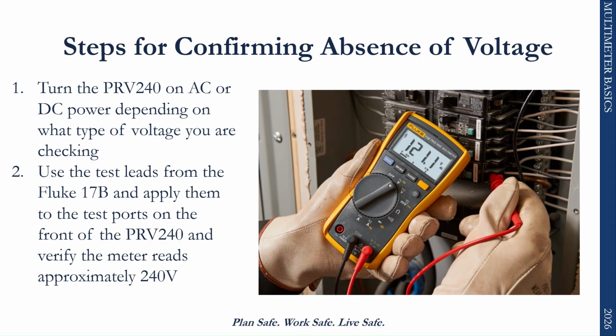The first step in the live-dead-live process is verifying that your meter is functioning properly. Start by turning on the PRV240 proving unit and selecting the appropriate setting depending on whether you are testing AC or DC voltage. Then place the test leads from the Fluke 17B onto the terminals of the proving unit. Your meter should display a reading of approximately 240 volts. This confirms that the meter is functioning correctly before you test the circuit.